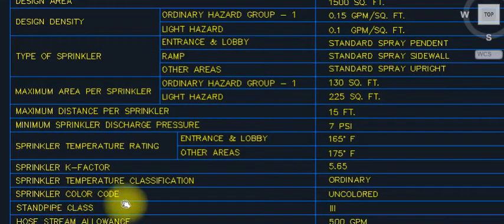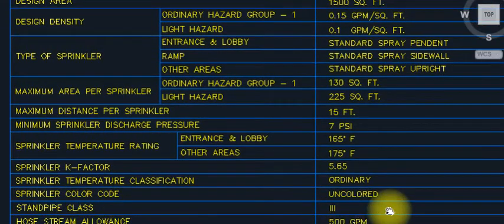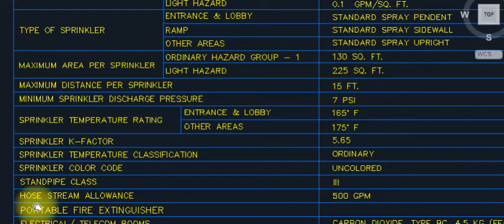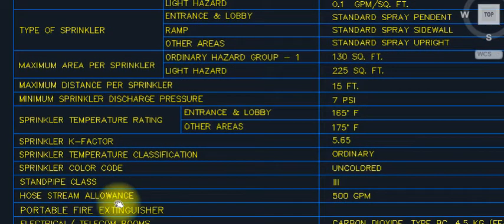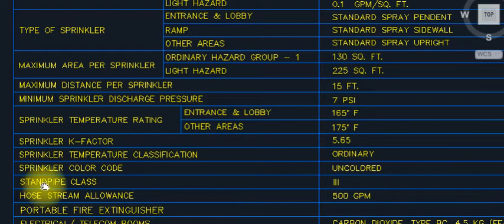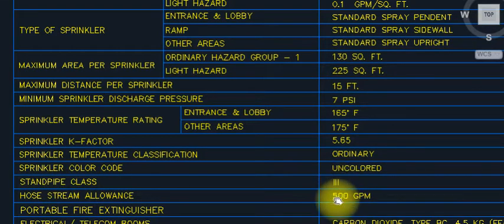Sprinkler color: uncolored. Hose stream allowance: 500 GPM. Standpipe class: 3.